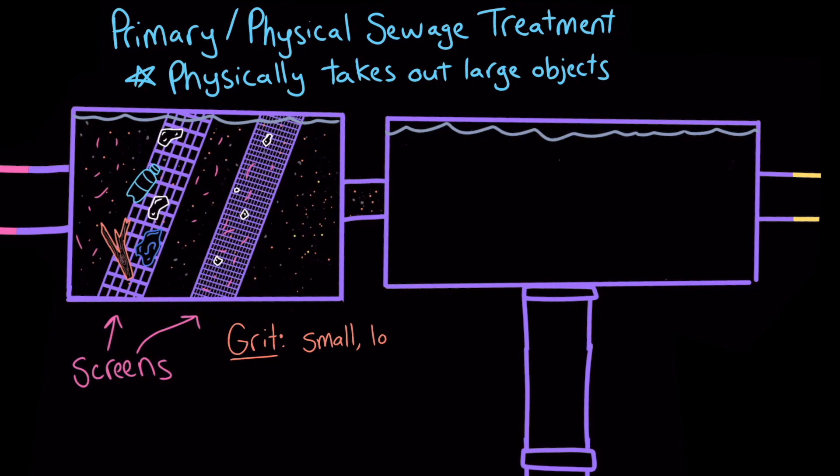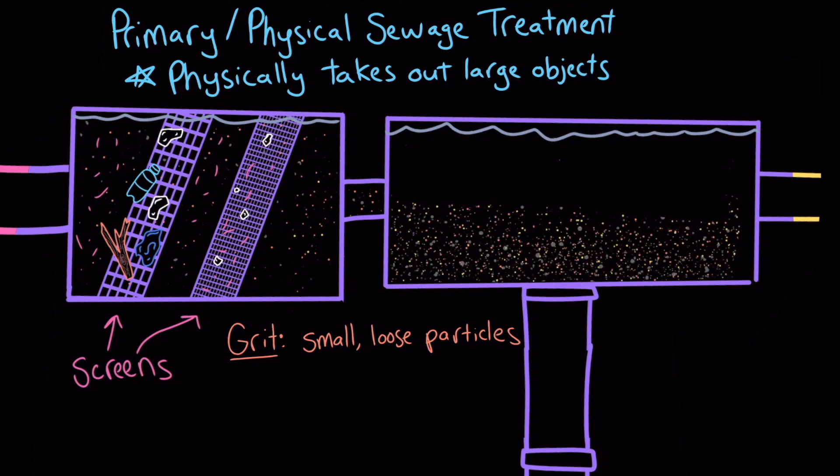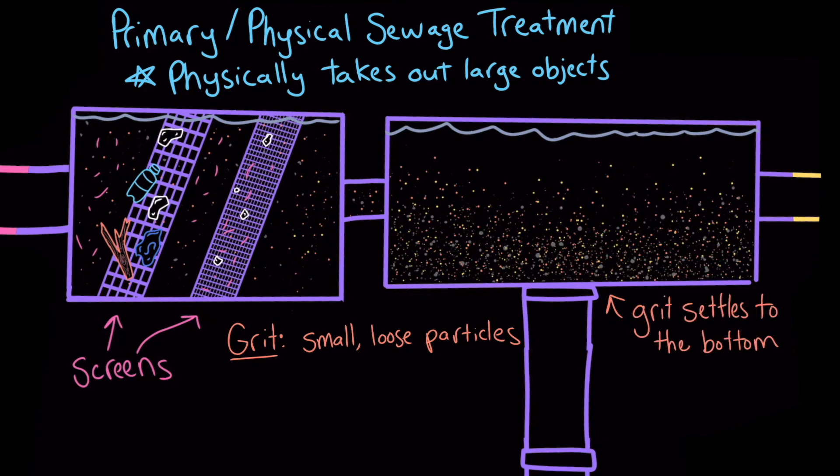Grit is made up of small, loose particles of sand, gravel, coffee grounds, food waste, and other pieces of material. To get rid of the grit, the treatment plant pumps the water through long, narrow tanks that slow down the flow enough that the grit has time to settle to the bottom. All that thick, soft mud that gathers at the bottom of the grit tank is called sludge, and it's collected and treated.